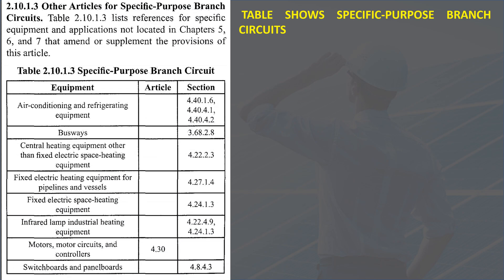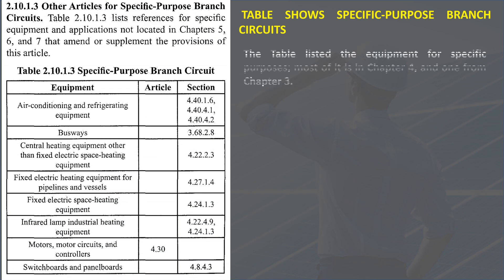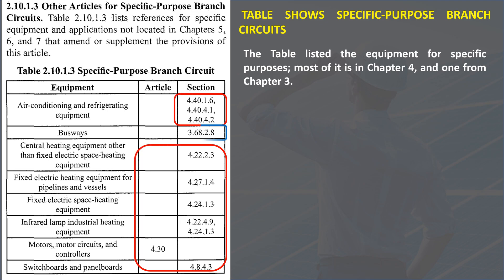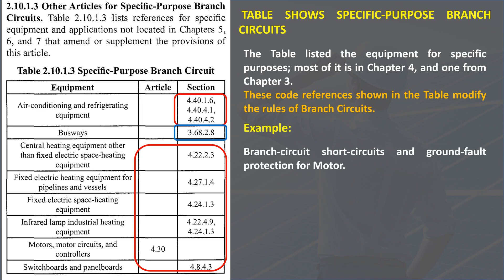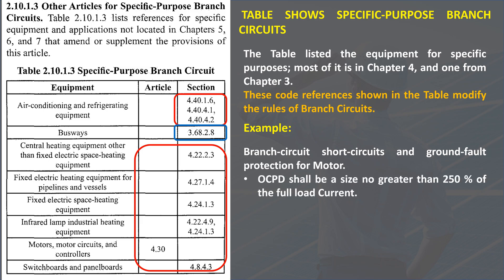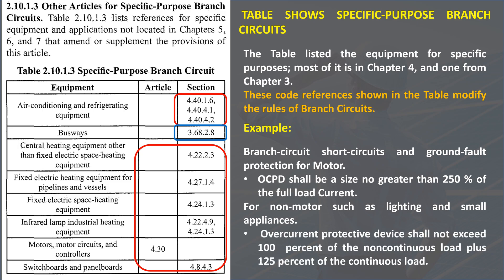The table lists equipment for specific purposes, most of it in Chapter 4 and one from Chapter 3. These code references shown in the table modify the rules of branch circuits. For example, for branch circuit short circuit and ground fault protection for motors, the overcurrent protective device shall be a size no greater than 250% of the full load current. While for non-motor loads such as lighting and small appliances, the overcurrent protective device shall not exceed 100% of the non-continuous load plus 125% of the continuous load.